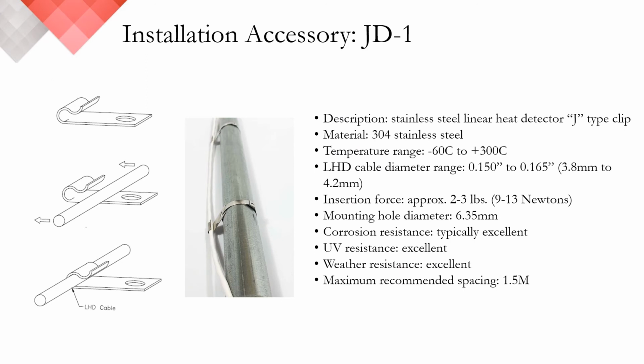Here we are featuring our newest mounting accessory, the JD1 clip. This fastener has been designed by us to perfectly accommodate the diameter of our linear heat detectors. This fastener is made of 304 stainless steel and can be either rack mounted or pipe mounted and paired with a stainless steel pipe strap. The advantage of this J-clip is that the fasteners can be installed before the detector, and or the detector can be easily removed for any splicing requirements.